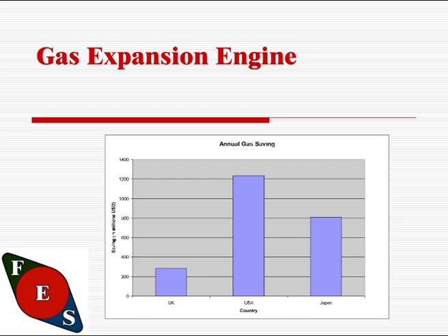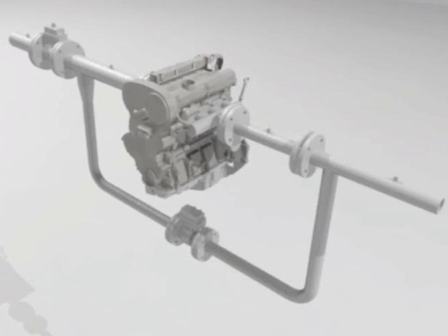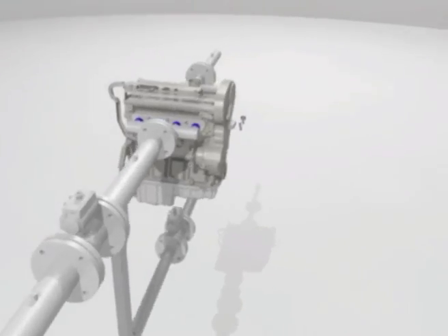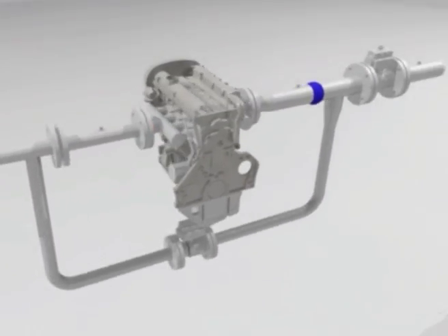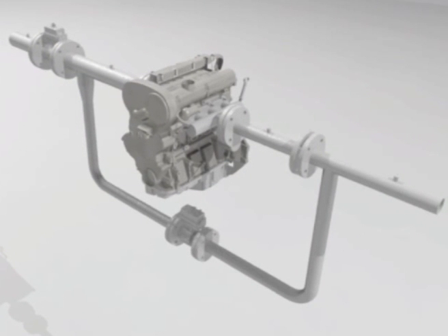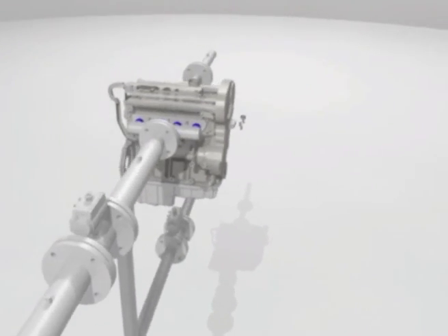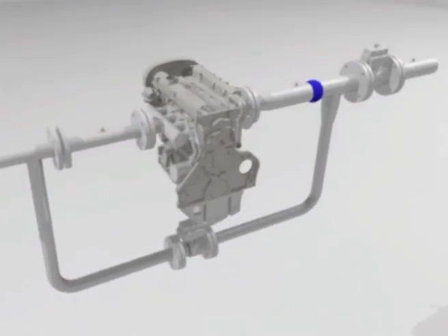Gas expansion principle. The gas expansion system is designed around extracting useful work through the process of depressurization. The supply gas is required to go through a throttling effect to reduce the feed pressure at certain stages of distribution. This depressurization makes no use of the energy initially used to pressurize the gas. Further to this, the depressurization causes the gas to cool, thus requiring preheating prior to pressure reduction to avoid potential corrosion of the pipe due to condensate formation. The fluid engine offers a solution to offsetting the preheating process costs and offering a reliable means of powering auxiliary pipeline equipment in isolated locations.